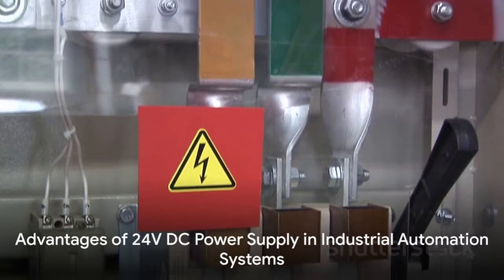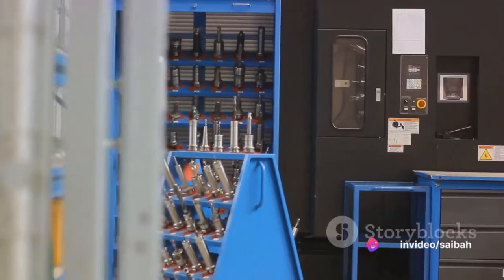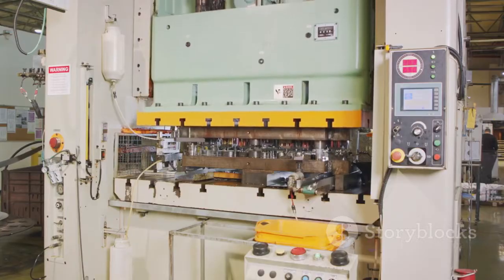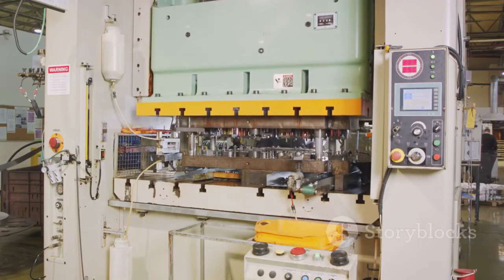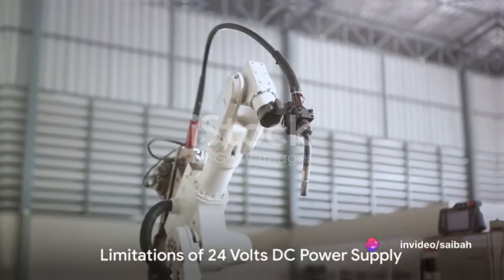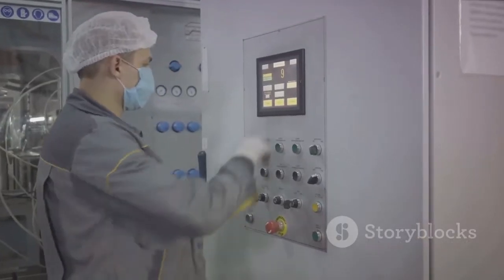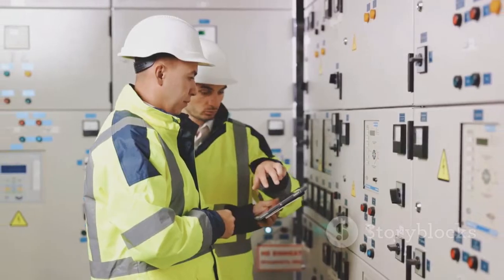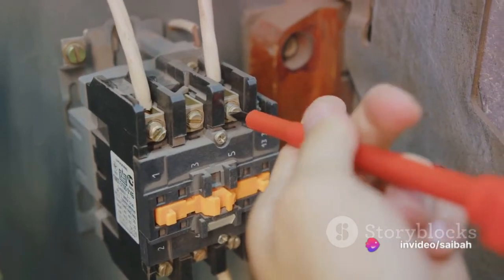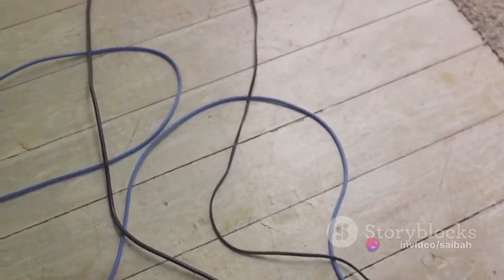All these advantages make the 24V DC supply a preferred choice in industrial automation systems. The multitude of benefits — from size and cost reduction to constant voltage output and noise immunity — make it a versatile and reliable choice for powering devices. However, like any technology, the 24V DC supply also has some limitations. There are a couple of key drawbacks to consider. The first relates to distance: the 24V DC supply isn't the best choice for long-distance applications.